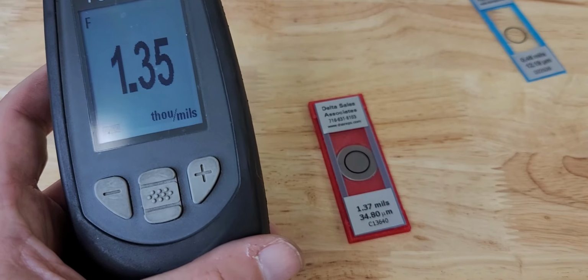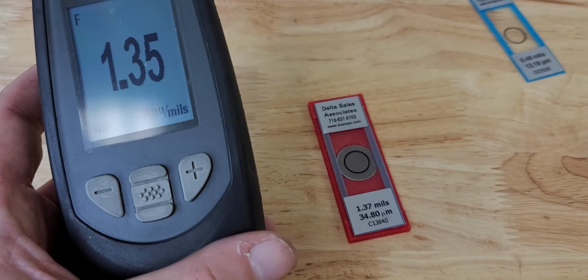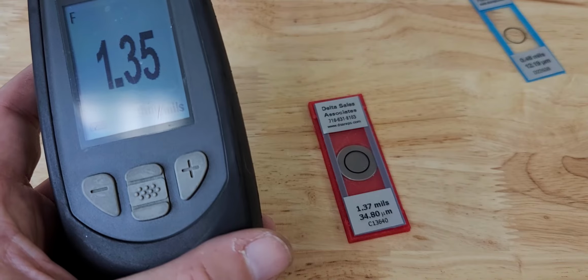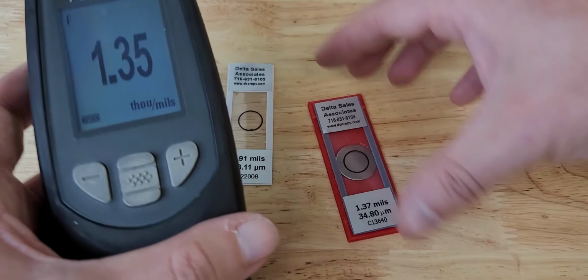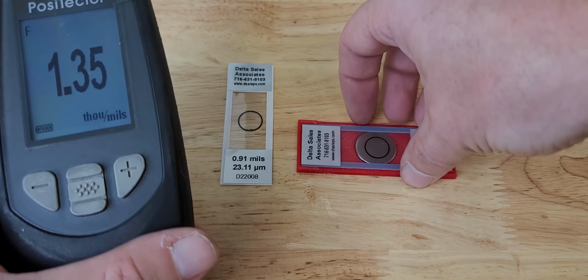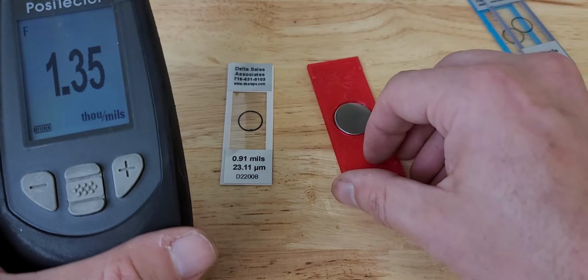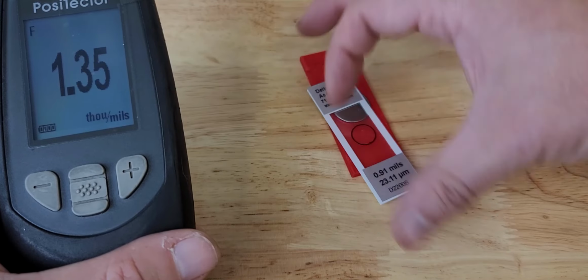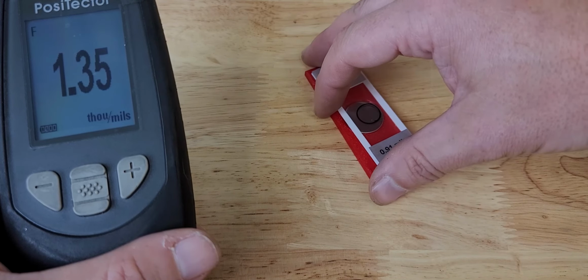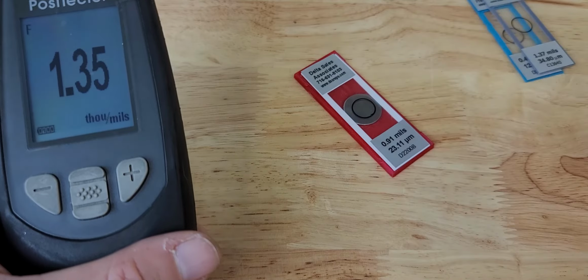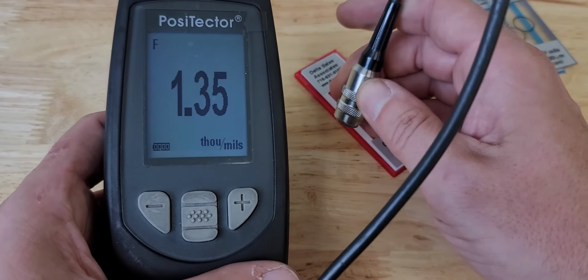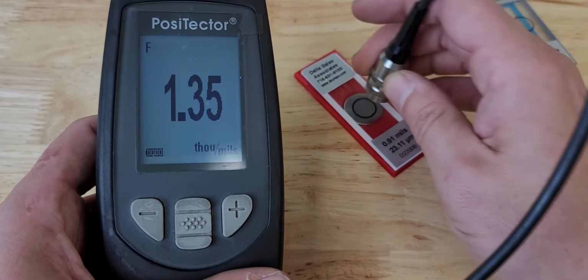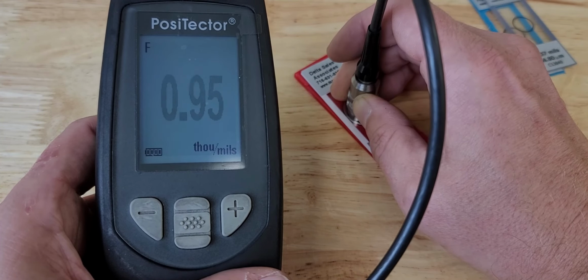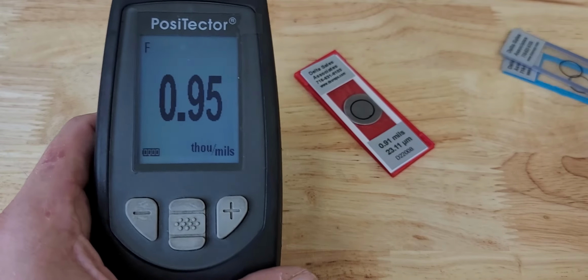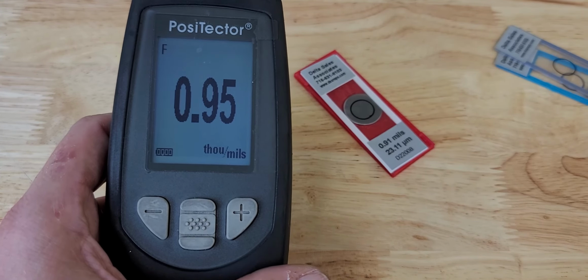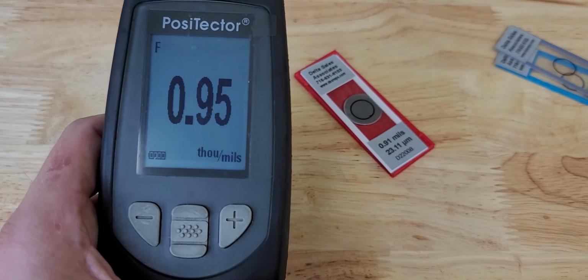The only thing left to do would be to do a verification, and I would highly recommend having a verification standard that's in the middle of your range that you want to coat, so you can test your calibrations. Obviously we've done the high and the low, but let's make sure now that the middle is good. I've got a 0.9 mil, 0.95 on it, and I would say that's going to be as good as we can expect off of this unit.